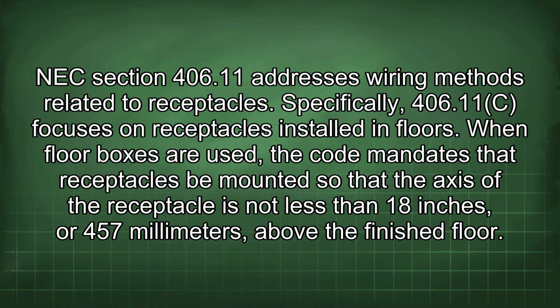NEC Section 406.11 addresses wiring methods related to receptacles. Specifically, 406.11c focuses on receptacles installed in floors. When floor boxes are used, the code mandates that receptacles be mounted so that the axis of the receptacle is not less than 18 inches, or 457 mm above the finished floor.